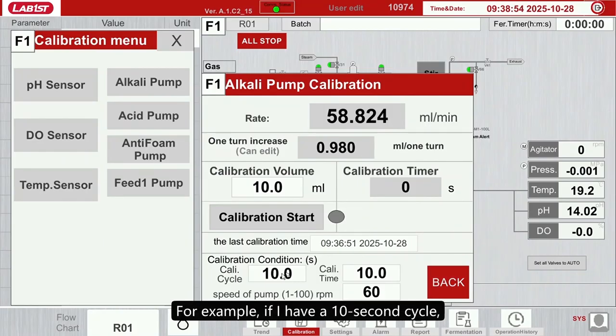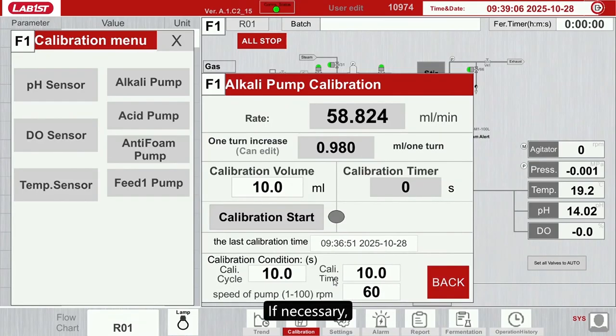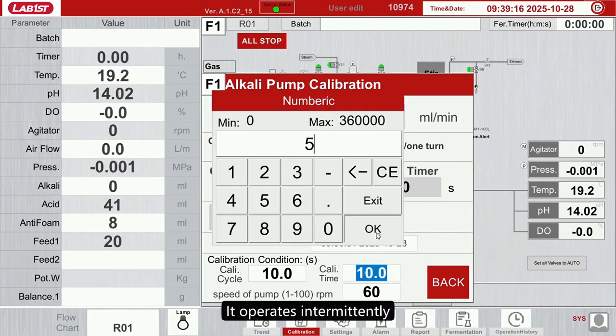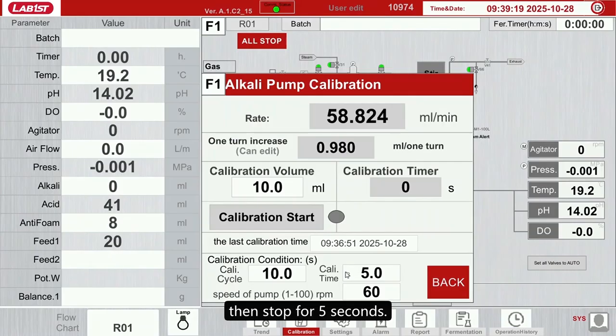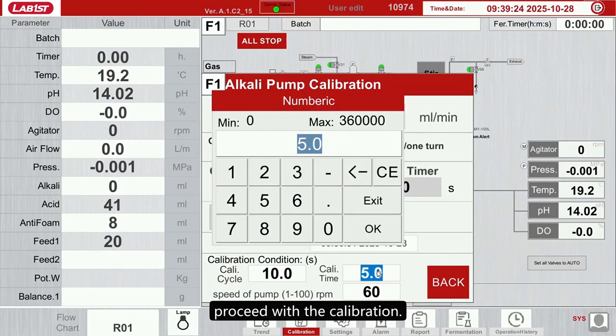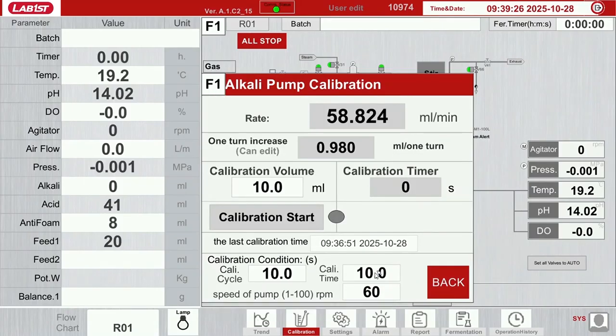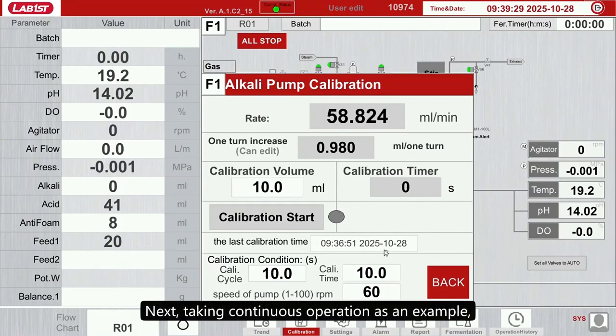For example, if I have a 10-second cycle, it should run continuously for 10 seconds. That is, it should run continuously at 60 rotations per minute. If necessary, according to the process, for instance, with a 10-second cycle, it operates intermittently, then stops for 5 seconds. Once you've set these conditions, proceed with the calibration. Next, taking continuous operation as an example.